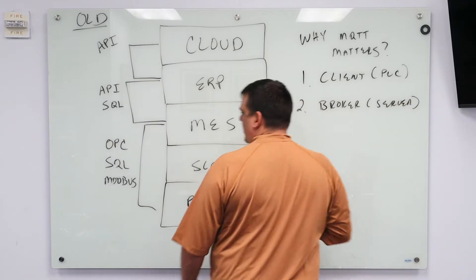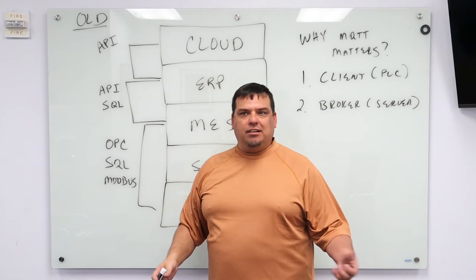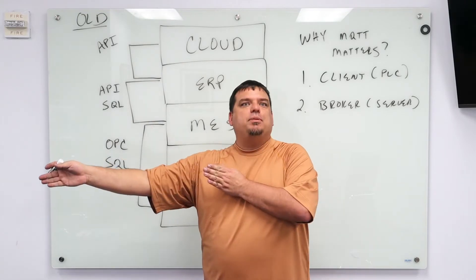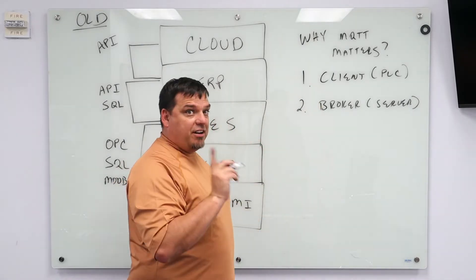In an old architecture we would have our OPC server like Kepware running on a Windows 2008 R2 machine and we'd have to point Kepware to the PLC in the field. That isn't the way this works. The device gets pointed to the broker. That's very important.